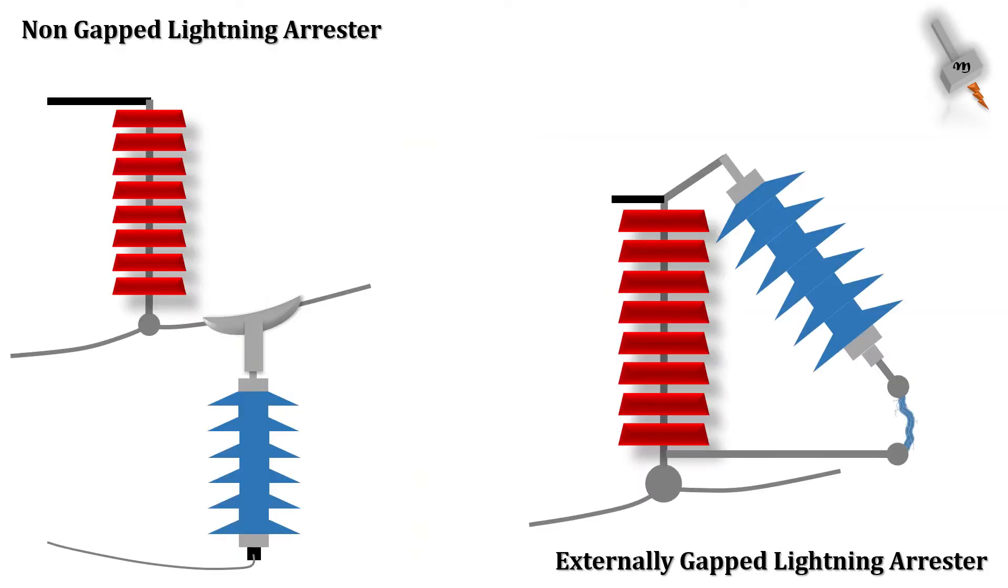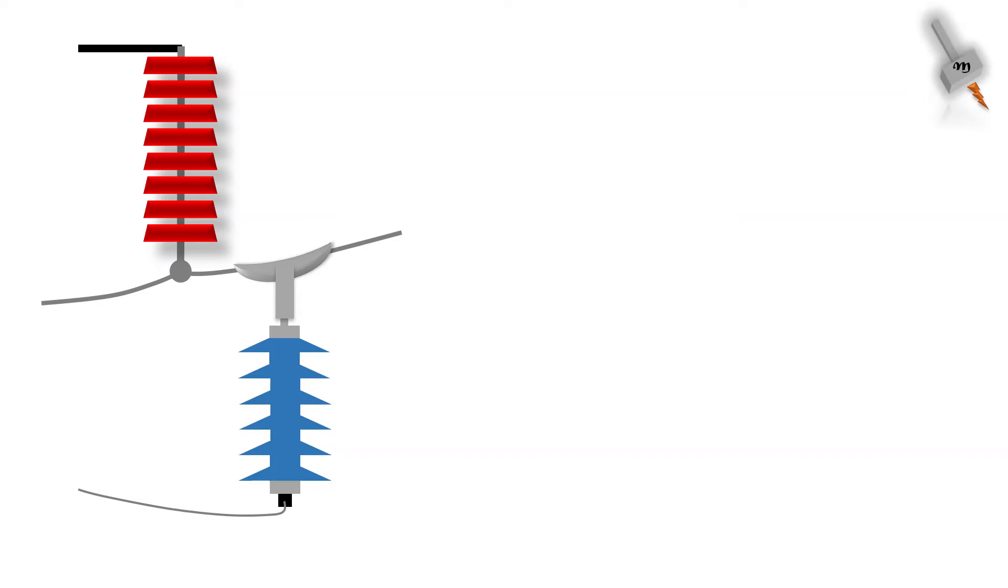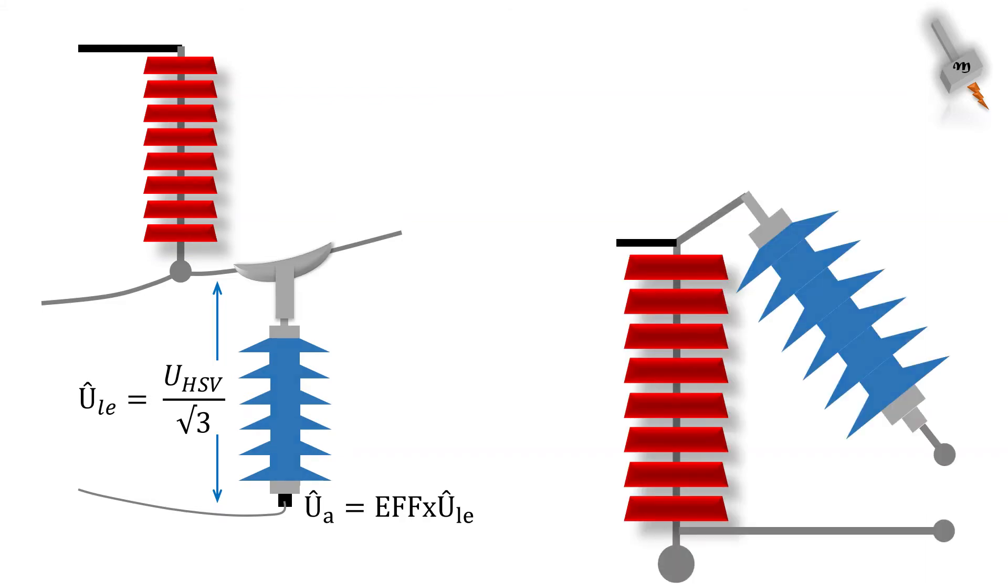Now let's move to see what are the other differences between NGLA and EGLA. For the NGLA, the continuous applied voltage across the arrester terminals is highest system voltage divided by root 3. The rated voltage of the arrester is earth fault factor times the continuous applied voltage. In EGLA, the rated voltage is same as the continuous applied voltage. This is due to the fact that the EGLA is meant to handle the lightning overvoltage and not the switching or power frequency overvoltage.